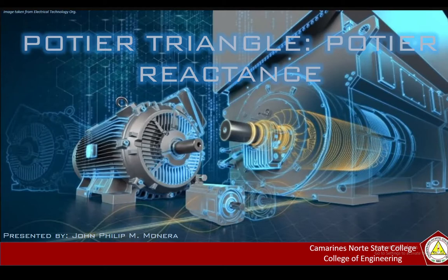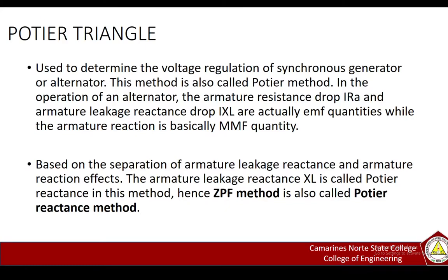The topic that I will be discussing today is the Potier triangle and the Potier reactance. The Potier triangle is used to determine the voltage regulation of synchronous generator or alternator. This method is also called Potier method. In the operation of an alternator, the armature resistance drop IRa and armature leakage reactance drop IXL are actually EMF quantities, while the armature reaction is basically MMF quantity, which is the magnetomotive force quantity.